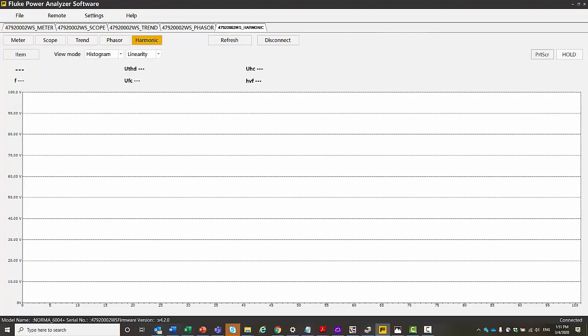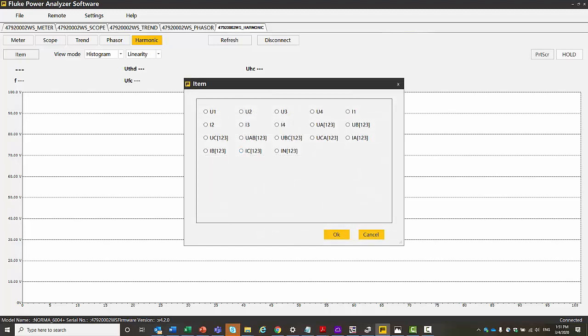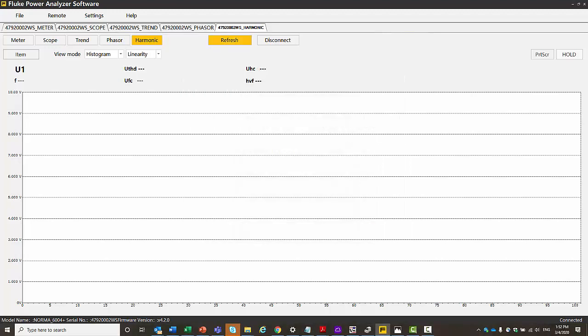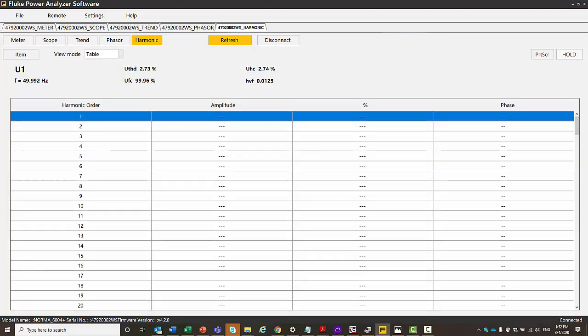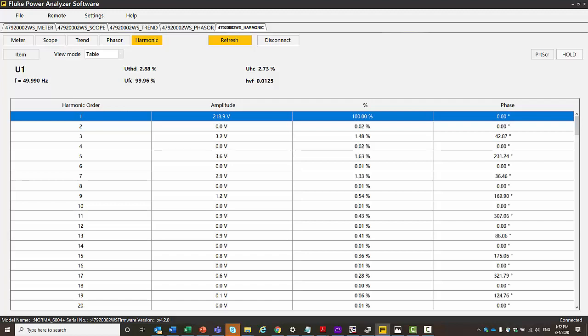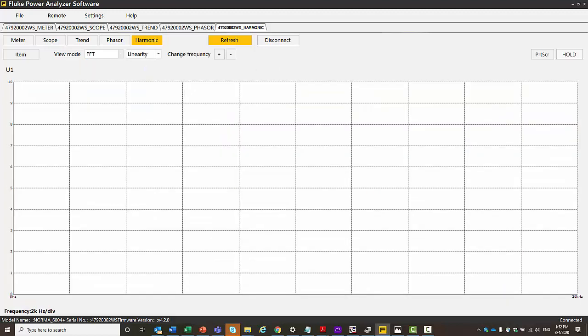And then similarly with harmonics, you can choose the type of harmonics that you have. So you go to the list, we'll choose U1. You can just have one at a time, and then we get the readings here, and we can see what it looks like. We can choose either the histogram or a table. You see that in the table we'll get some values in a moment, or we can also choose the FFT.